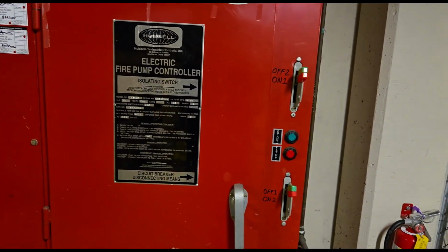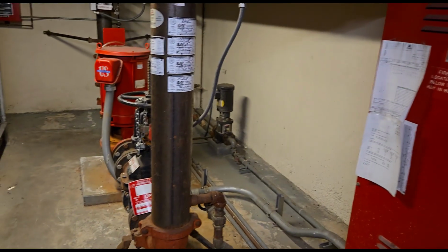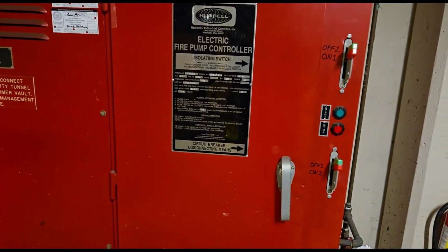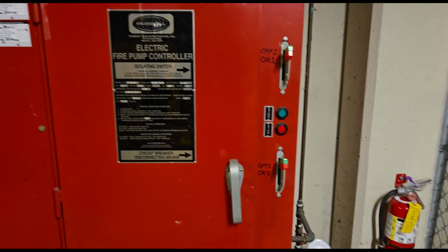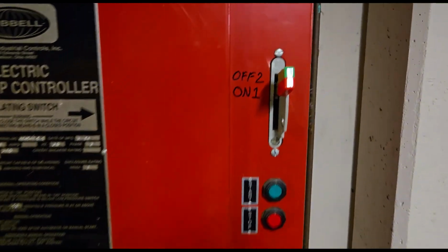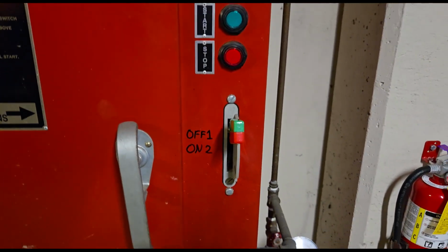They don't have a contract with our company for the sprinkler or for any pump testing. They just have it for alarm testing, so we're only going to focus on the alarm system. We're going to bypass the pump. So, off 2, off 1 -- circuit breaker off first, isolating switch off second.